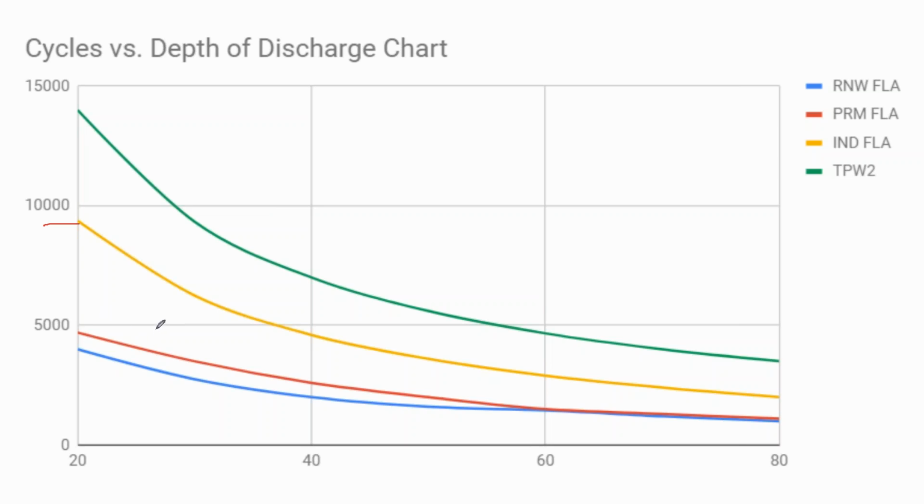And so, sometimes, where we kind of erred on my first off-grid design is we went for a well-sized industrial flooded lead acid battery, and it's going to last for decades based on its average depth of discharge.